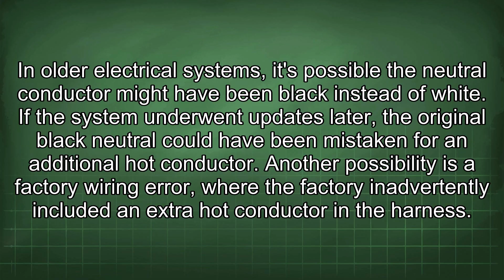In older electrical systems, it's possible the neutral conductor might have been black instead of white. If the system underwent updates later, the original black neutral could have been mistaken for an additional hot conductor. Another possibility is a factory wiring error where the factory inadvertently included an extra hot conductor in the harness. It is also possible that the original installer may have employed non-standard wiring practices, such as using a different color code for the hot conductors. The extra hot conductor may have been installed as a backup in case one of the other hot conductors failed.